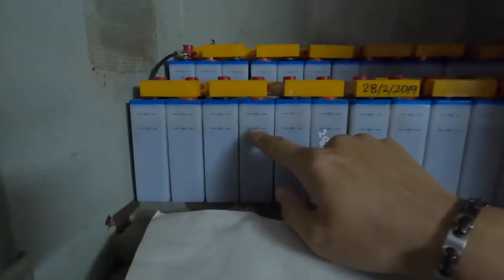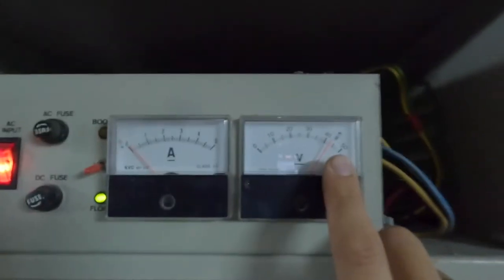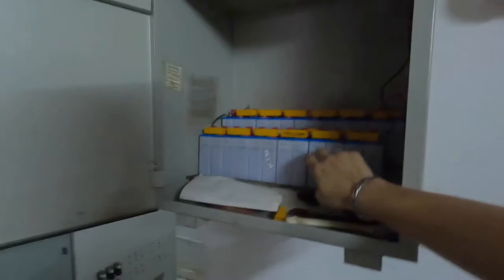This is a nickel-cadmium battery. Battery water level needs to be topped up — it's a little bit low here. The voltage is a little bit high, somewhere around 40V. We're going to use a voltmeter to clarify that later on.